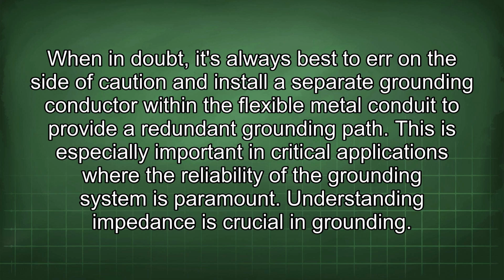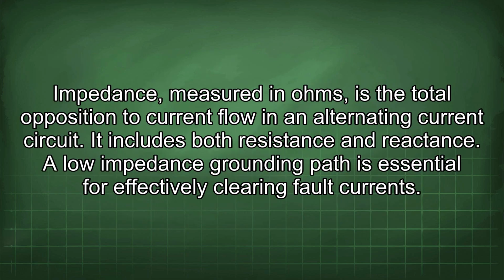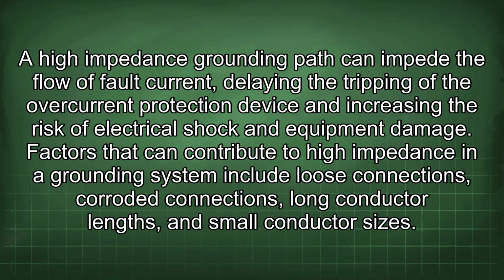Understanding impedance is crucial in grounding. Impedance, measured in ohms, is the total opposition to current flow in an alternating current circuit. It includes both resistance and reactance. A low impedance grounding path is essential for effectively clearing fault current. A high impedance grounding path can impede the flow of fault current, delaying the tripping of the overcurrent protection device and increasing the risk of electrical shock and equipment damage.